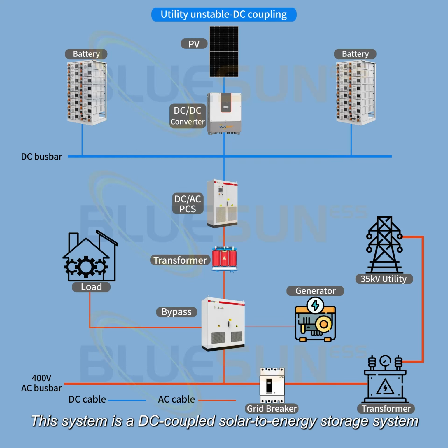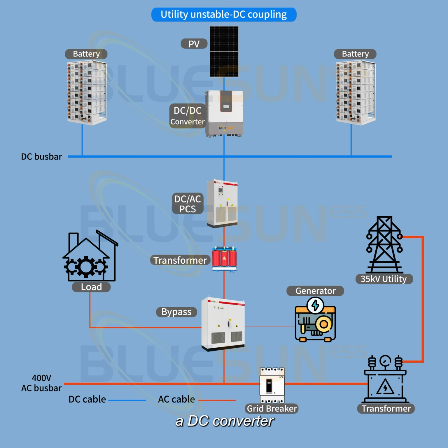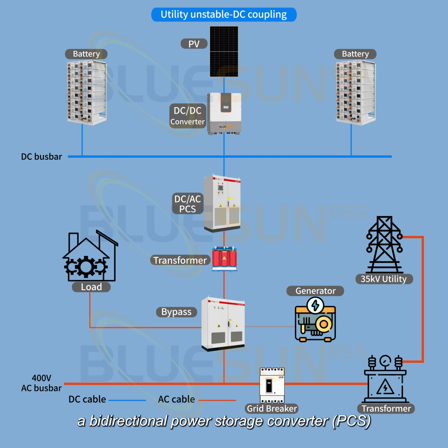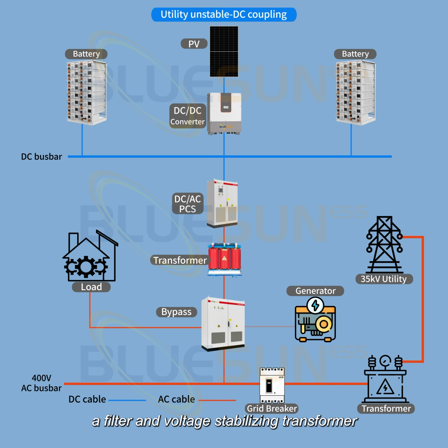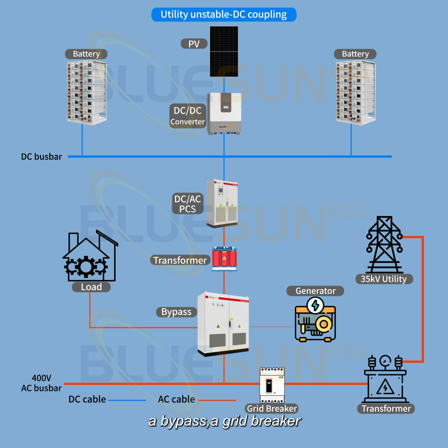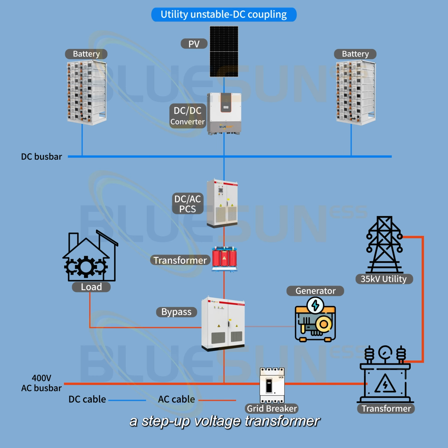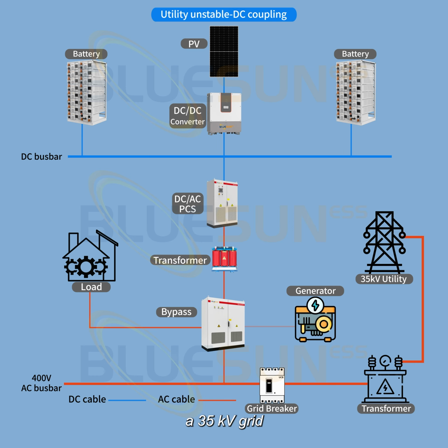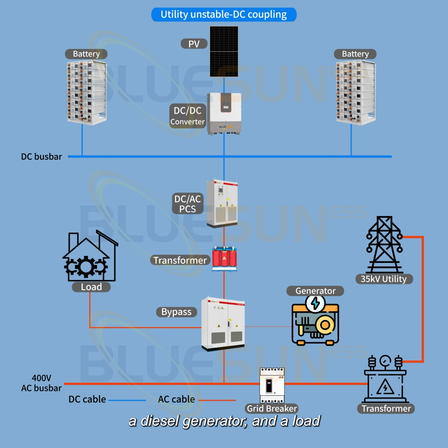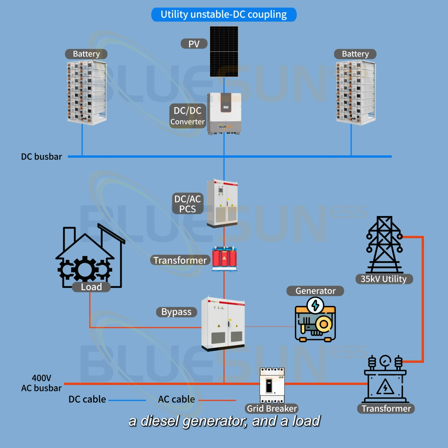This system is a DC-coupled solar-to-energy storage system with UPS functionality, offering a stable, practical, and reliable structure. It consists of PV panels, a DC converter, a bidirectional power storage converter (PCS), a filter and voltage stabilizing transformer, a bypass, a grid breaker, a step-up voltage transformer, a 35 kV grid, a diesel generator, and a load.